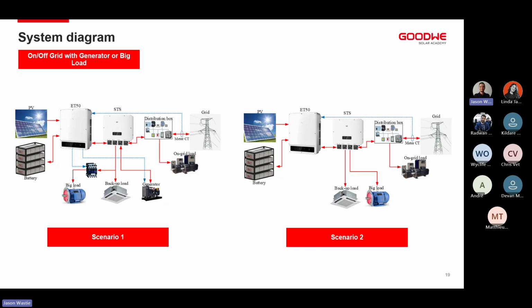If we go to scenario number 2 on the right-hand side, it works in the same way. However, we are using the physical generator port as the secondary AC output. So the generator port is dual purposed. It can be used either for one generator integration or for a secondary AC output that is configurable.